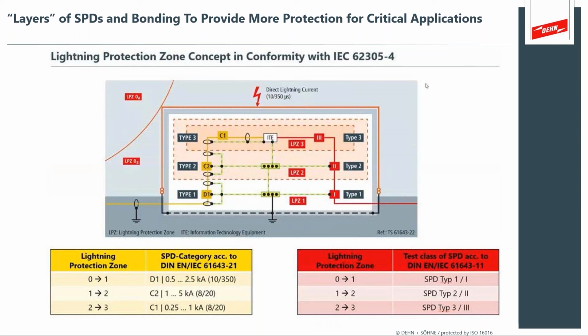No, I agree 100% with you. The test procedure in the IEC standard allows us to calculate or measure the continuity through the reinforcing. We do that by means of that 10 amp injection current test. The standard says we have to calculate or measure a continuity of 0.2 ohms or less. Only then can we use the reinforcing as part of our down conductor system. Otherwise, we have to install external down conductors. With some of our applications, we run conductors inside of the reinforcing as well to ensure this continuity when we are early enough on the project. But obviously, if you're on a project that is already being costed, it's a bit difficult.